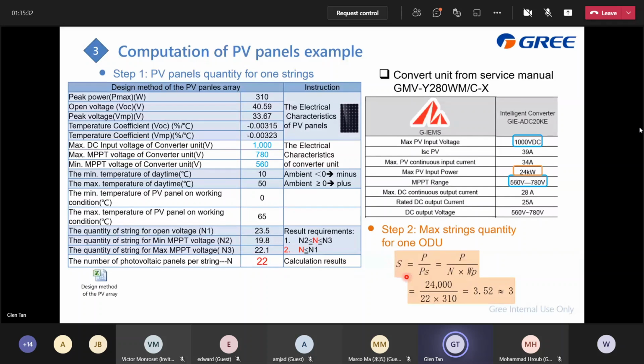And for this one, we can get the max PV input is 24 kilowatt, and from this formula, we can get it is only 3. That means for this model in your local, there are 3 strings of the PV panels, and in each string there are 22 PV panels.